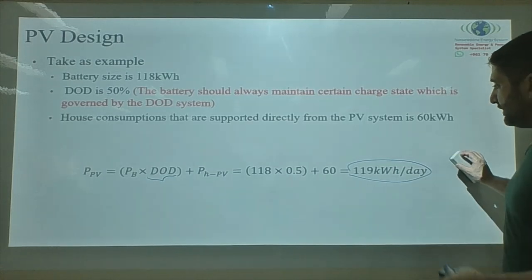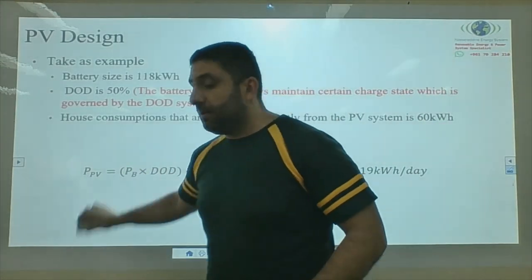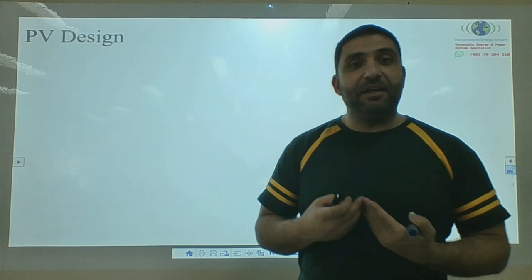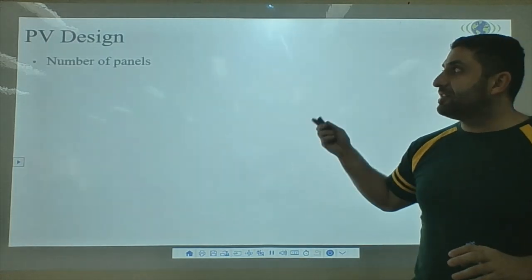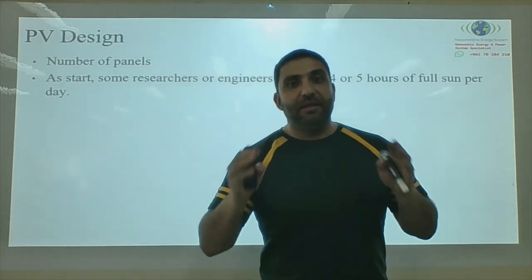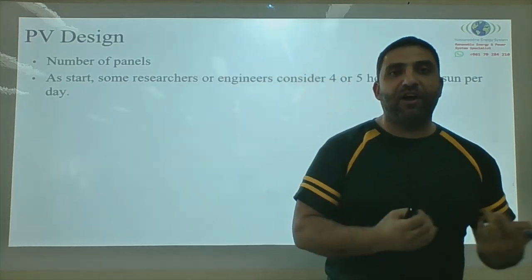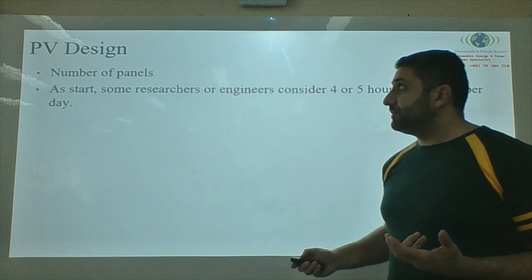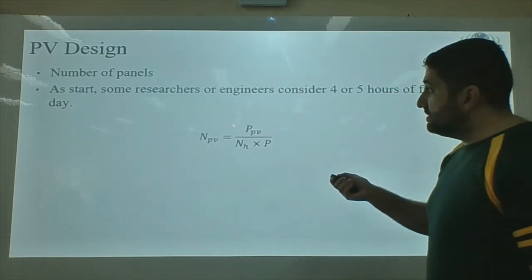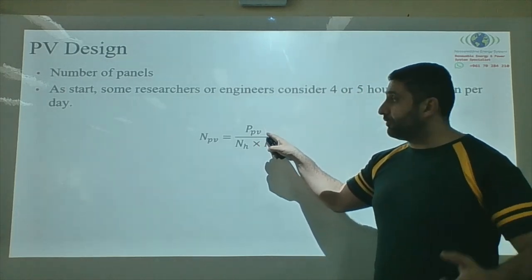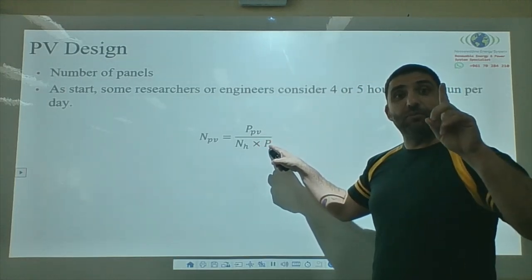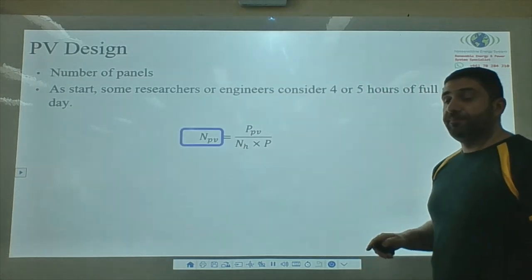With 119 kWh per day required, determine the number of sun hours available as covered in lecture two. The number of panels required equals the calculated PV power divided by the single panel power (e.g., 250 W or 360 W panels) divided by the number of daily sunlight hours. This gives the total number of panels needed for the system.